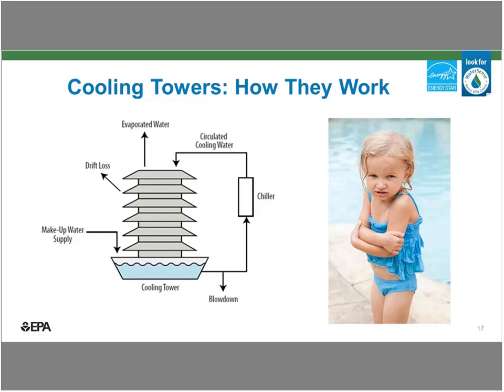So we have everyone oriented to the discussion, I want to just take a moment to go over some of the basics of cooling tower operation. The concept is fairly simple. Water and air flow past each other, typically in a countercurrent or cross-flow configuration. In this schematic illustration, water is introduced at the top and flows down while air is drawn up through the tower by a fan. As the air passes over the water, some of it is evaporated, which removes heat and reduces the temperature of the water in the tower.